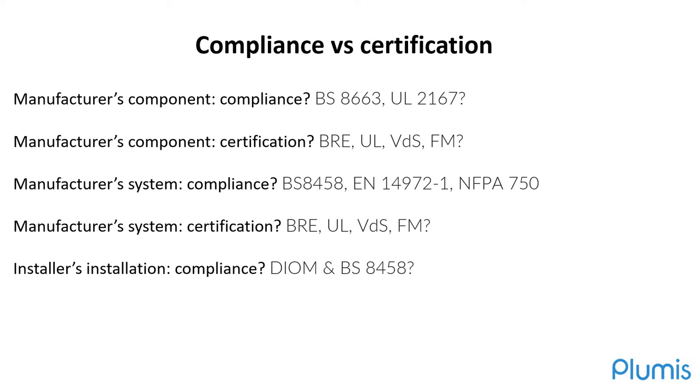It's important that in the watermist world, the DIOM comes hand in hand with a standard, as opposed to what typically happens with sprinklers, where there's no real DIOM, there's just the installation standard like BS9251, which captures the best practices in how to install sprinkler systems, which tend to be all the same, so there's no need for a DIOM in that sense. And finally, we can have installer certification, where there is a scheme like BAFE or FIRAS, where the installer gets scrutinized to ensure that they have the competence to install the systems that they've been certified to do.